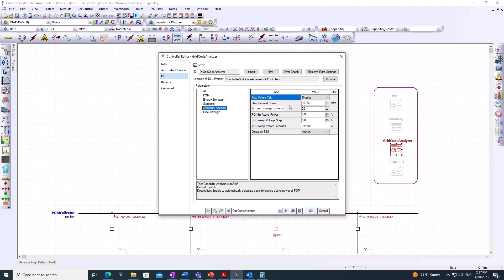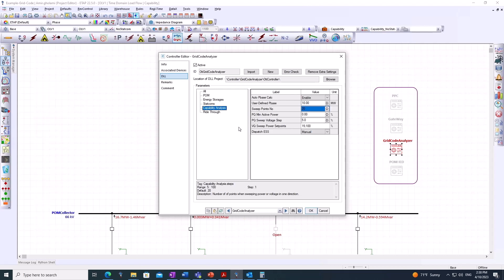We have multiple settings which define the P base — either automatic or manual — and the number of sweepings for P and Q as part of the automation of grid code analysis. The user can choose the minimum active power from which the sweeping starts, and also the voltage step used for presentation of results. This is a three-dimensional study involving active power, reactive power, and voltage. The user can define at which active power set points they want their VQ curves to be plotted.